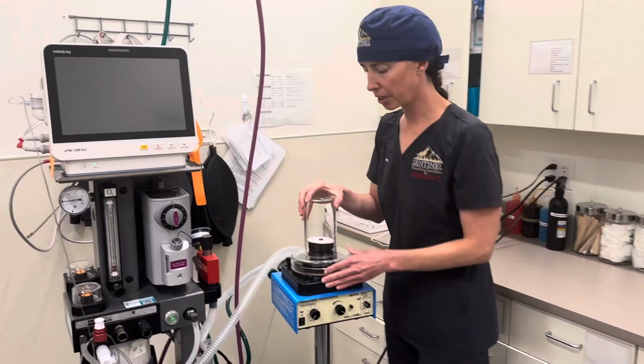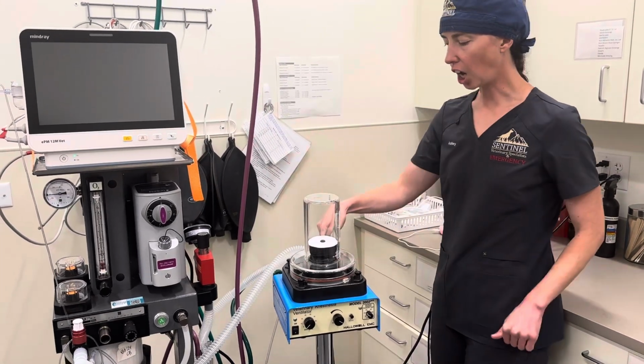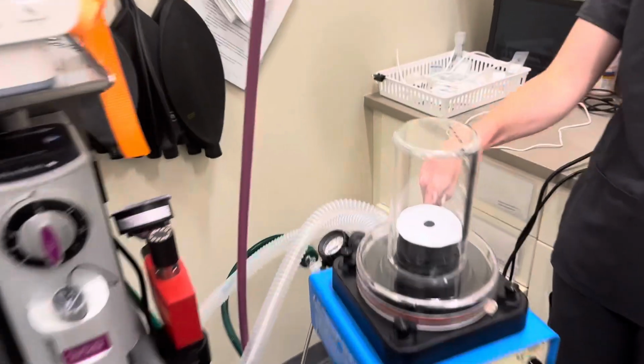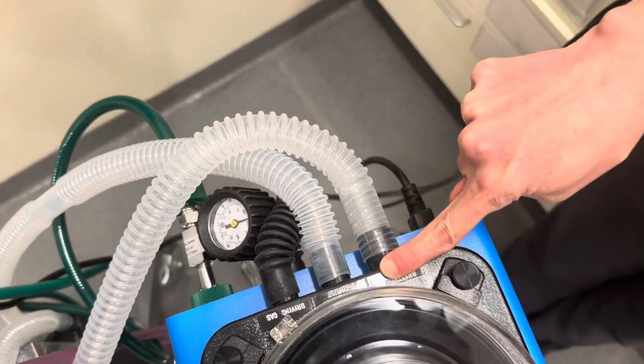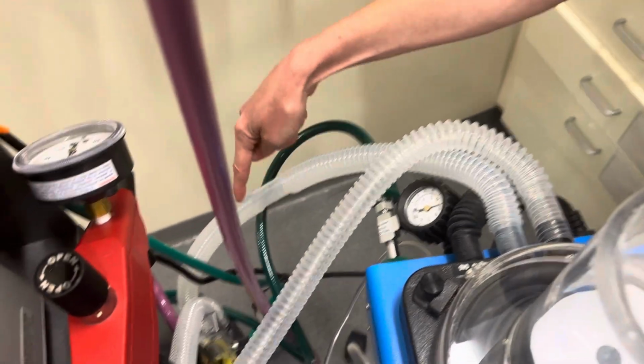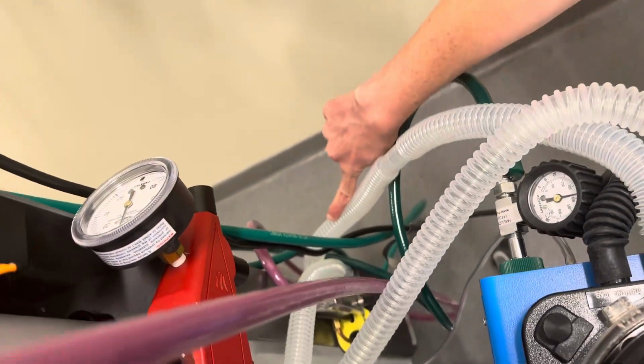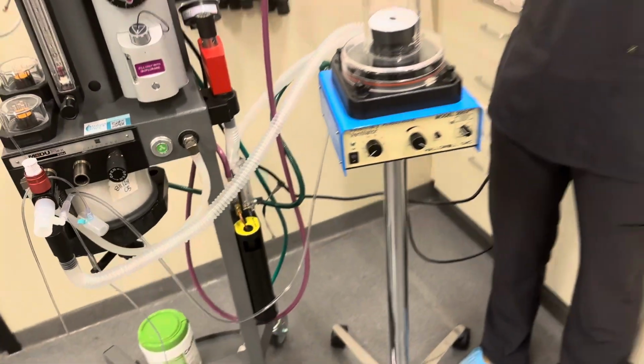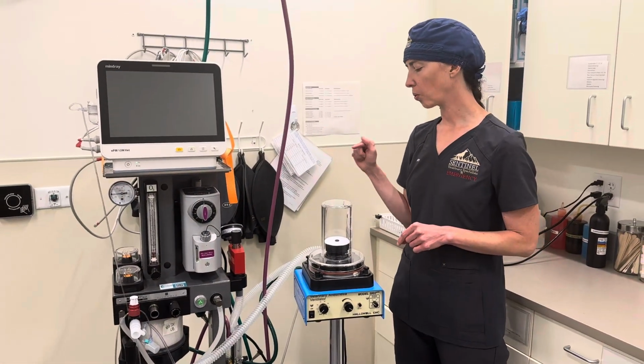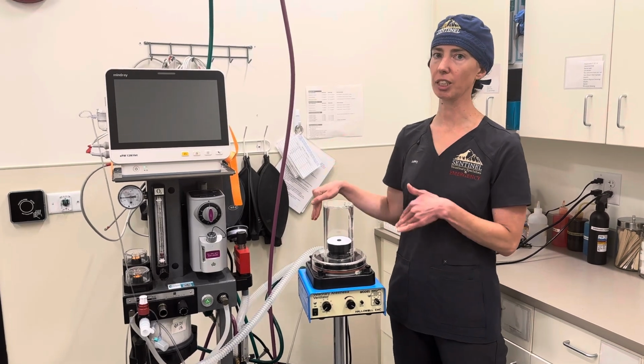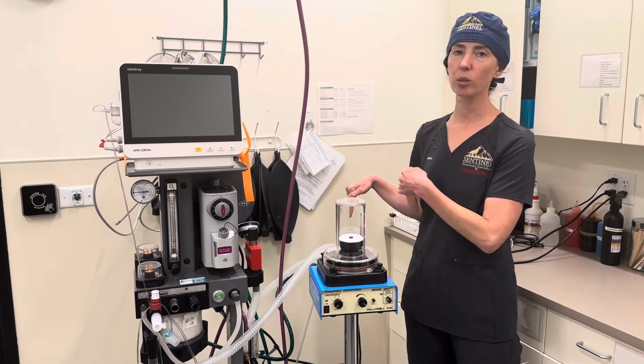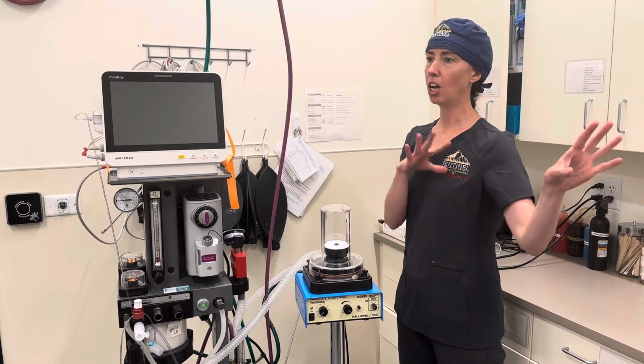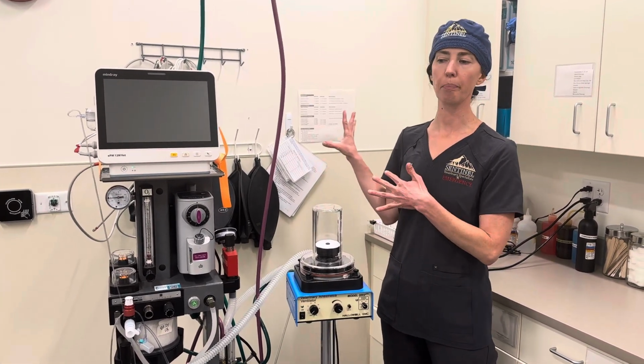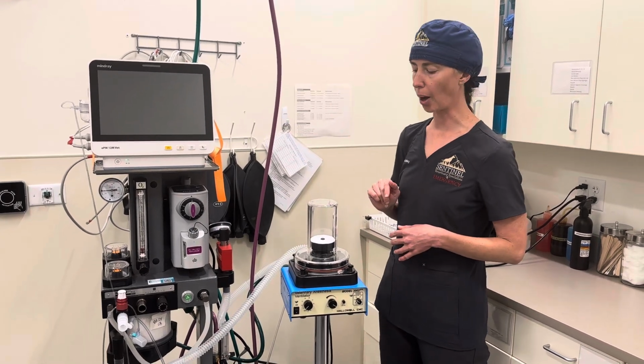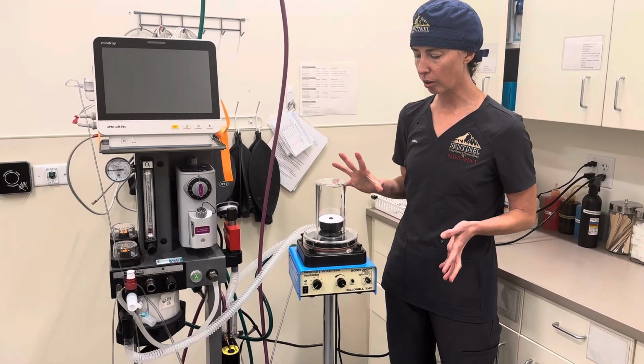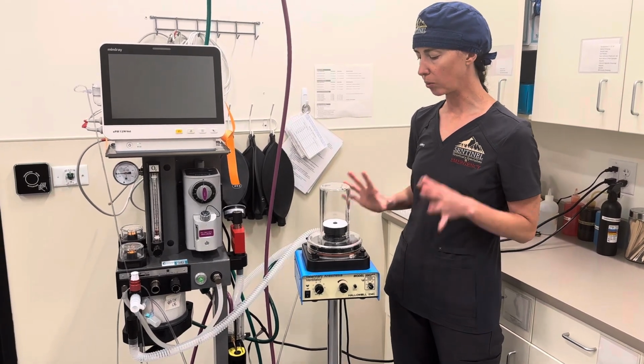And then the other part of these machines is there's an exhaust hose, and it says here on the back, exhaust, which is this guy right here. You just want to make sure that this hose is hooked up to the exhaust system on your machine. Every anesthesia machine often has a different scavenge system, so we need to make sure that where it says exhaust, that's actually hooked up to our scavenge system, because that's the hose that is going to make sure all the isoflurane gases are scavenged away from us and away from the operating room, back into the walls, wherever they go. So that's kind of the basics of how this machine works and how it's set up.